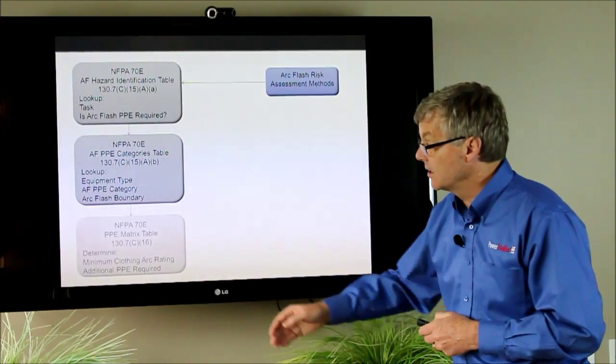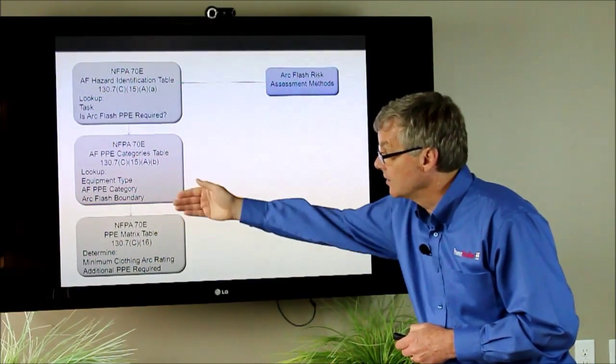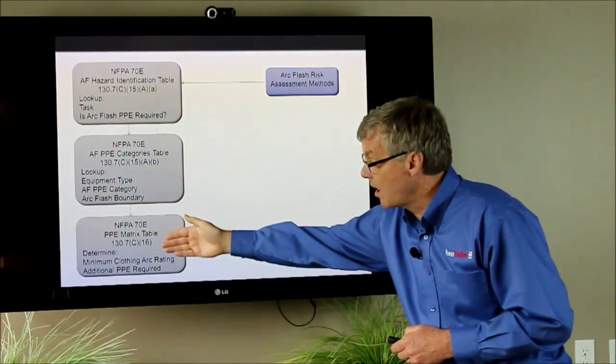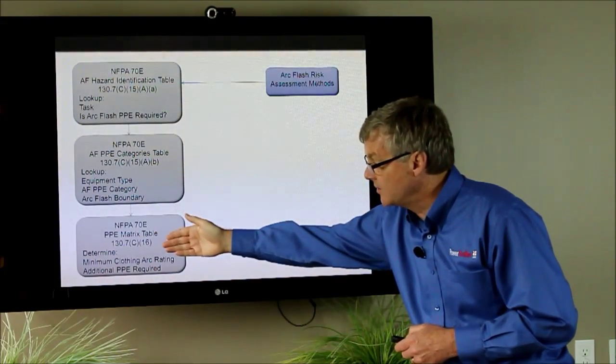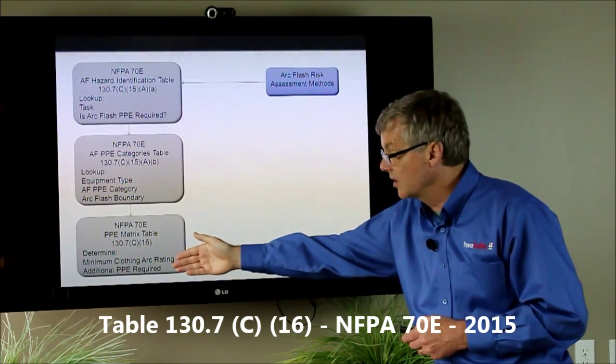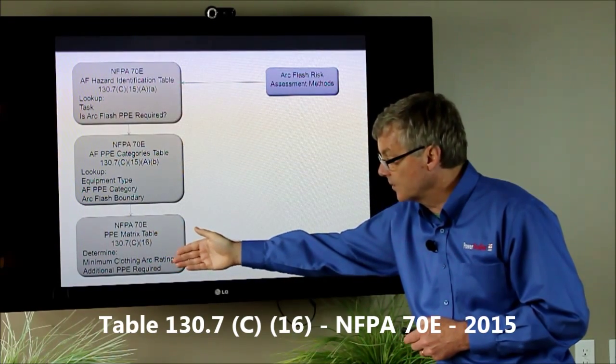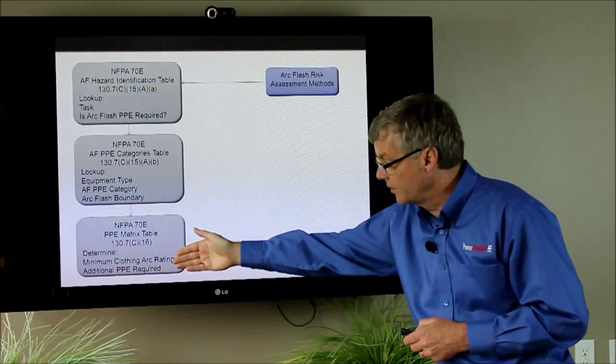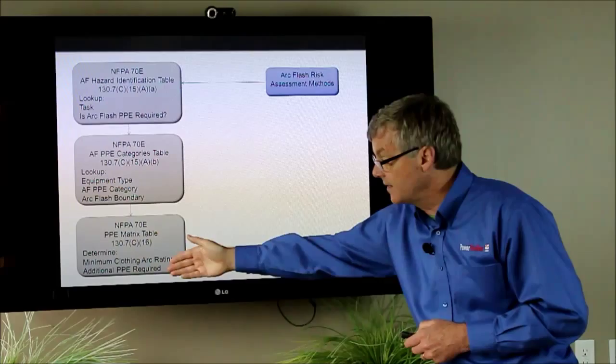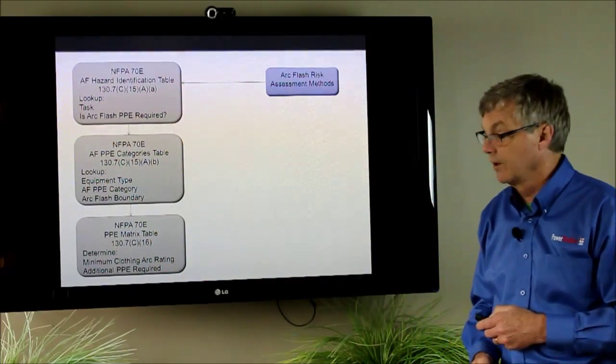The next method, after you've done this you determine what your arc flash category is, then you go to the arc flash PPE matrix table 130.7C16. There it's going to tell you what the arc flash clothing you're going to wear and the minimum arc rating in calories per centimeter squared and any additional PPE that you're going to have to wear.